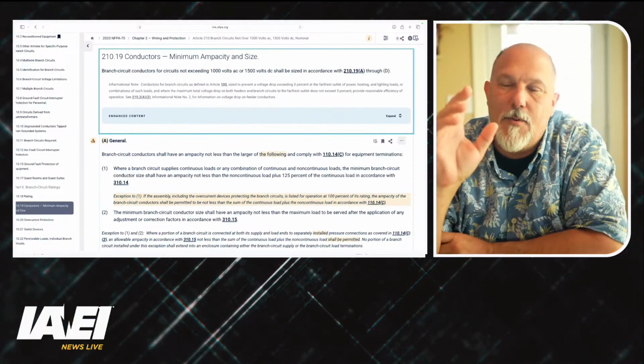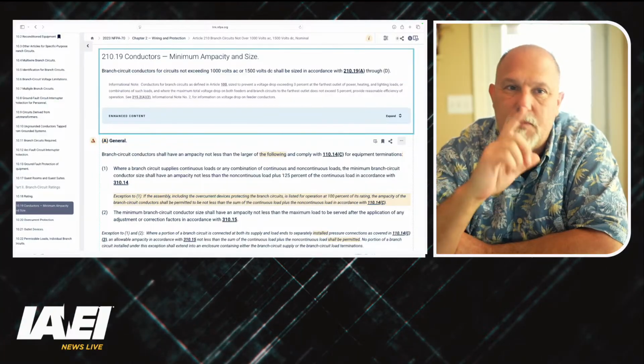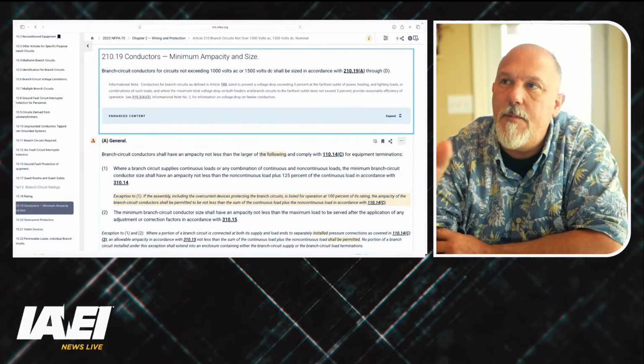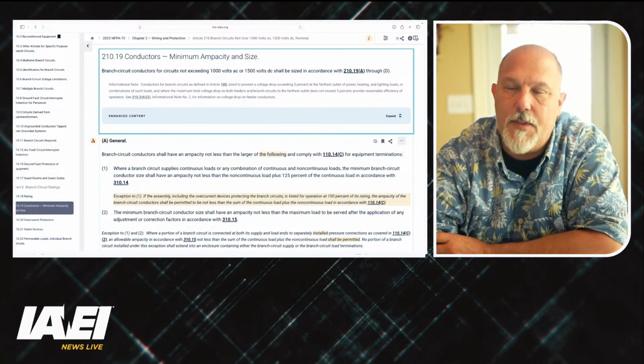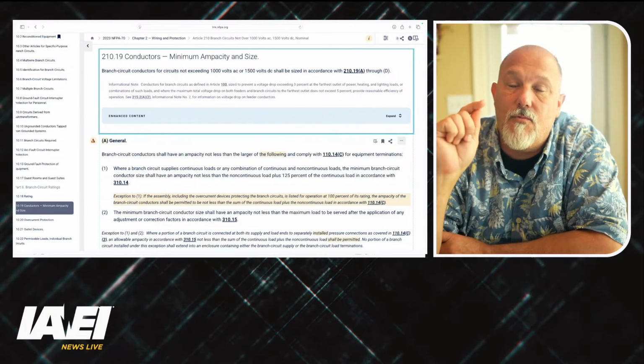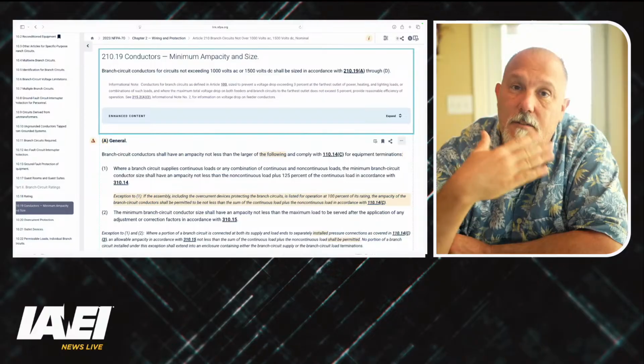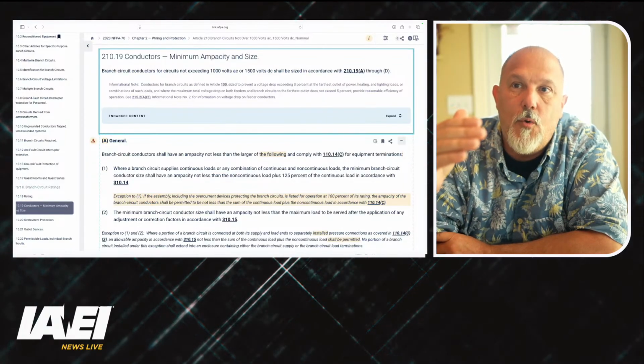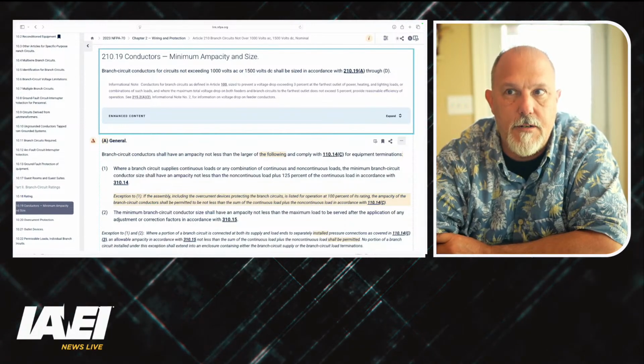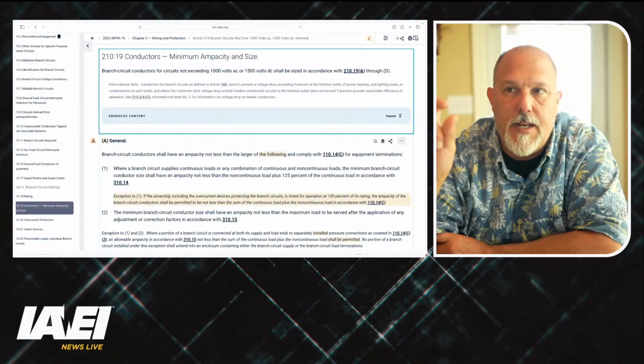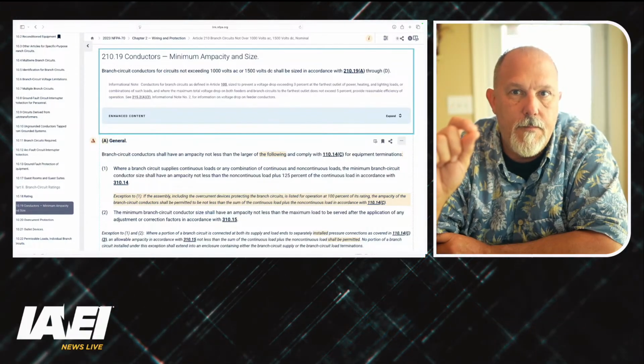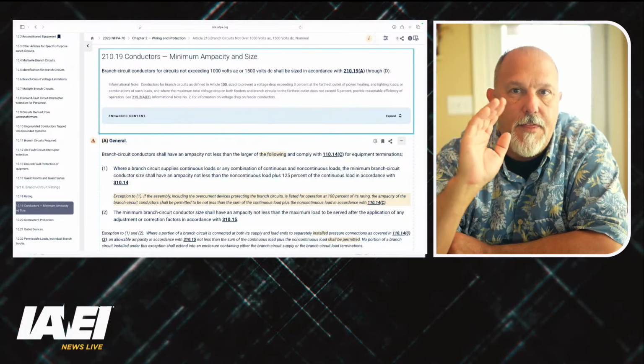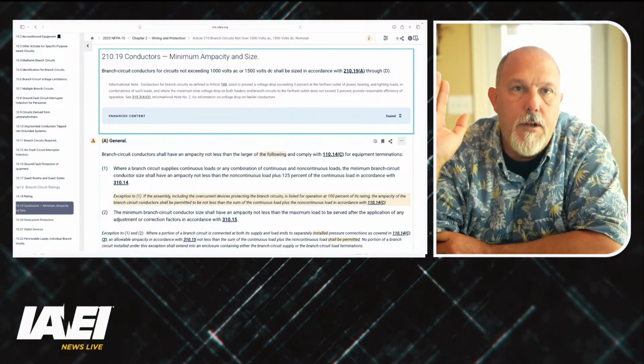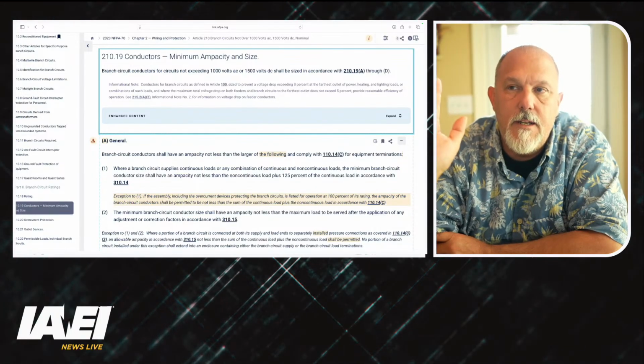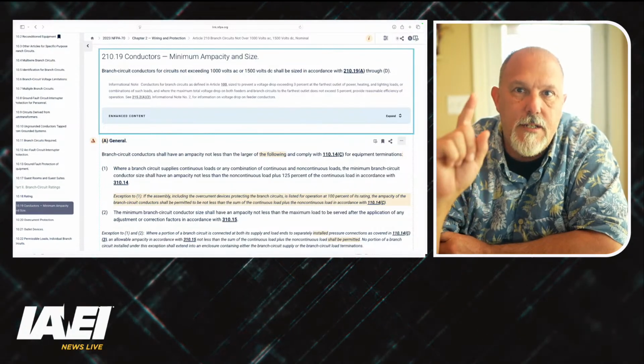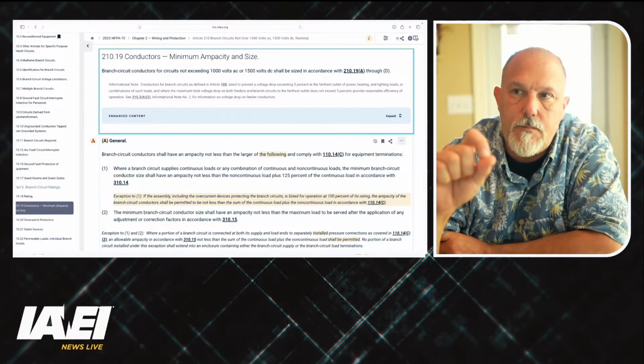I remember this comment. I can't remember where it came up, but I know it was on one of these programs because it was a chat. We said, okay, minimum ampacity and size, and we can lose the size because we already have it with ampacity. And the reason that's not right is, in fact, if I look back at some of my educational stuff, we end up picking up the right conductor. But I took the advice of somebody and I combined A1 and A2, picking a value of current and then going straight to a minimum size. That's not quite accurate and correct. And here's why.